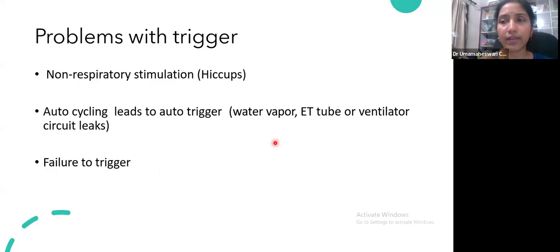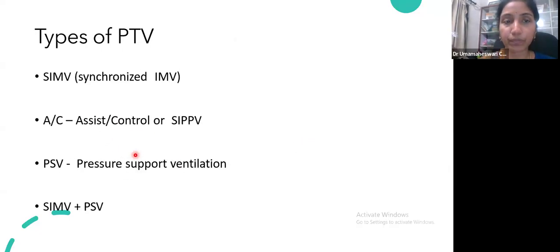So what is the problem with the trigger? Sometimes a non-respiratory stimulation can cause a trigger. The major problem is auto-cycling or auto-triggering, which happens majority of the time due to humidification. There can be water droplets in the inspiratory limb, which trigger. So sometimes the ventilatory rate can go even up to 100 if there is auto-triggering. You need to identify that and fix it. Sometimes whenever there is an ET leak, or you have put a smaller size tube, that can also simulate a difference in the flow, and that can get sensed. Sometimes it can fail to trigger.